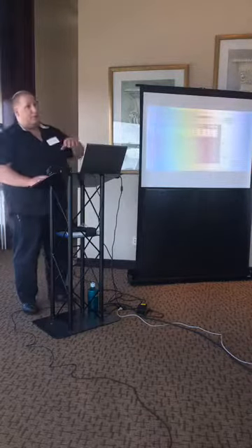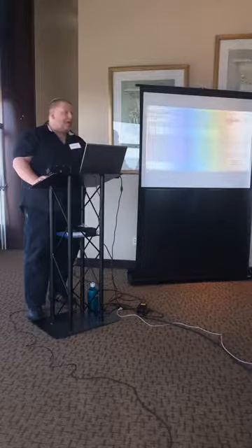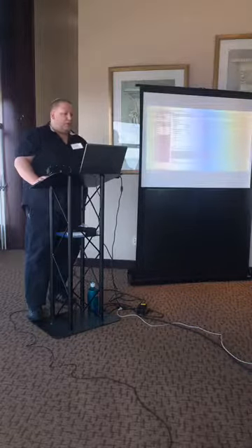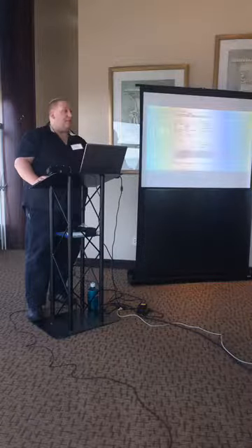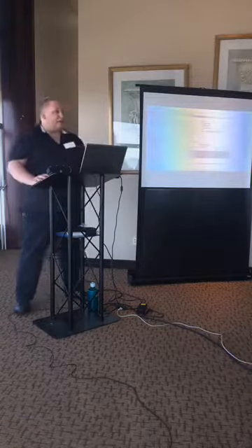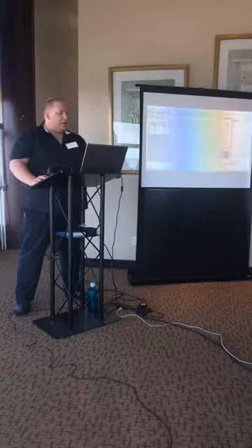You could take this operating point to a manufacturer and they'll give you a pump curve, or you can search directly within Fathom itself. And so if you click on this little pump icon with the spark coming out of it, that's the size of pump button. When you click on that, I'm going to use pump number 25 as my reference, because I want to make sure I minimize the head rise that's needed and the power draw. And I'm going to search the internet for a pump curve that will fit.